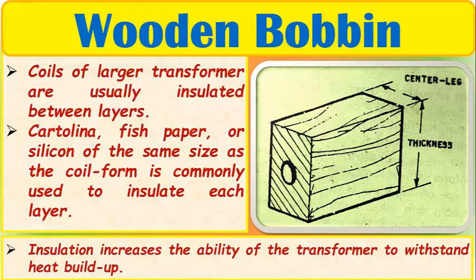Winding coils of a large transformer is done on a wooden former. It is used to support a coil form holding the coils. To make a former, cut a square or rectangular piece of wood 3.5 inches long. Drill a hole at the center of the bobbin so it can be inserted onto the shaft of the winding machine. Make the diameter of the hole a little bigger than the shaft. In a rectangular type of bobbin, one side is equal to the measurement of the center of the iron core. The larger side of the bobbin equals the thickness of the core. So this is now the picture of a wooden bobbin.